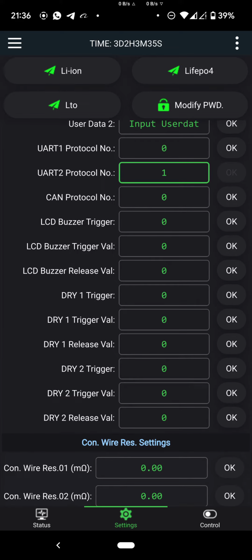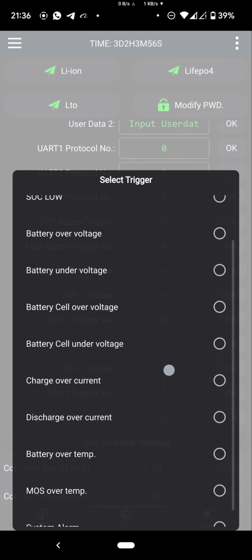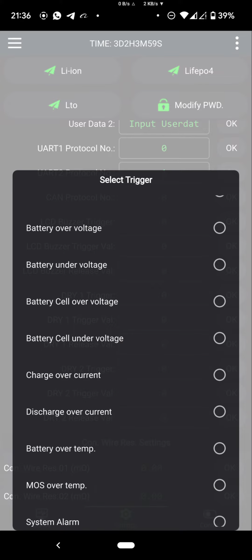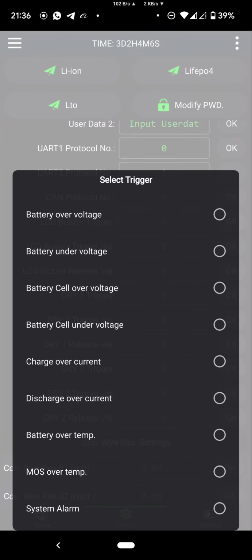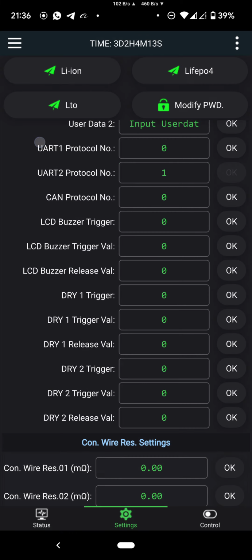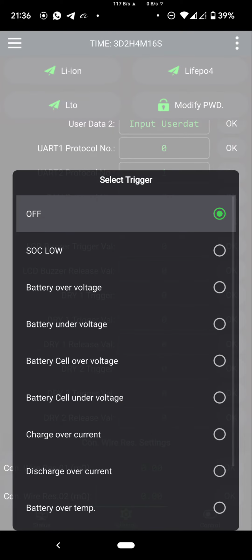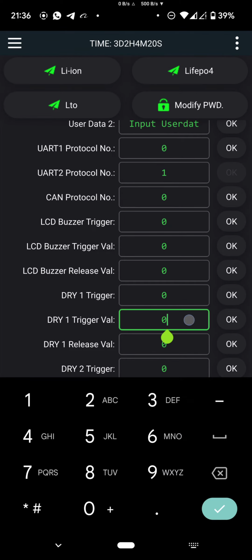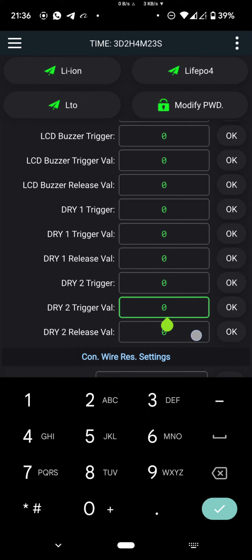Another addition to the parameters and features is the dry contact triggers. So as you know, the communication board has normally open and normally closed triggers, dry contact. So we have some options to trigger with. Let's see. So state of charge low, over voltage for whole battery, under voltage for the battery, cell over voltage, and cell under voltage, charge over current, discharge over current, and some temperature for battery and MOSFET, and some system alarms. Let's check the second one. All the same. And we can set a trigger and release for these 2 triggers.